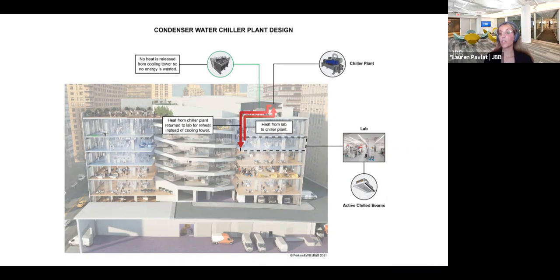With this scenario, the chiller plant is the same size. However, with DOAS we're reducing fan energy, needing a lot less air since we're also reusing water, and in turn the main ducts and shafts end up being reduced in size. This strategy is particularly important for energy saving in lab buildings like 125, since lab buildings are inherently energy intensive with such a heavy interior cooling load all year long.